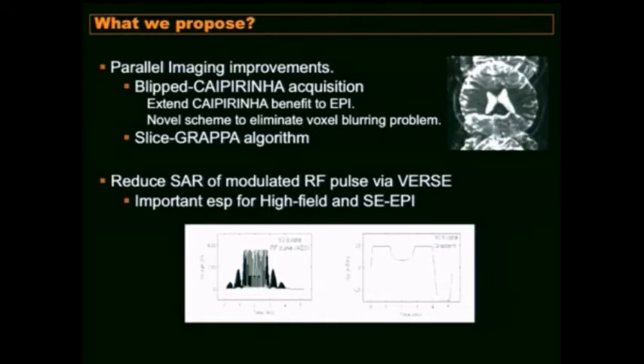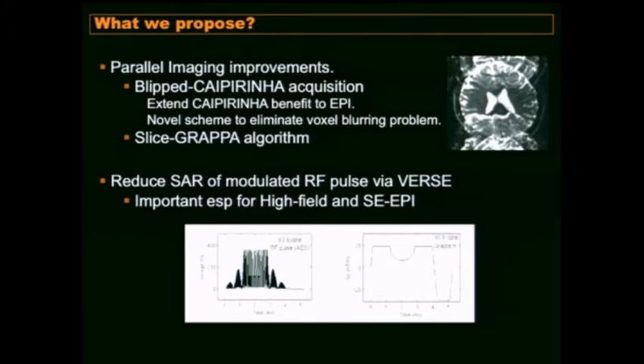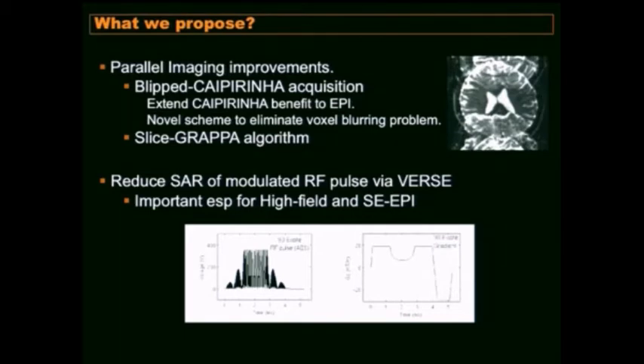I propose improving the parallel imaging method to achieve the blipped-CAIPIRINHA effect for EPI without the voxel blurring problem. That covers the acquisition part. I also propose a Slice-GRAPPA algorithm to reconstruct these collapsed images. Finally, we want to control the SAR — specific absorption rate — since exciting multiple slices at once deposits more RF energy. The RF pulse must be designed to give good excitation without too much SAR penalty. I'll focus on the first two topics for this part of the presentation.